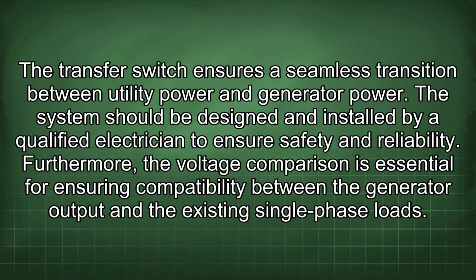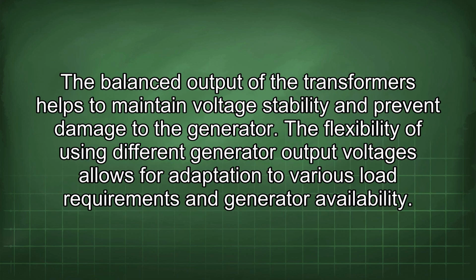Furthermore, the voltage comparison is essential for ensuring compatibility between the generator output and the existing single-phase loads. The balanced output of the transformers helps to maintain voltage stability and prevent damage to the generator. The flexibility of using different generator output voltages allows for adaptation to various load requirements and generator availability.